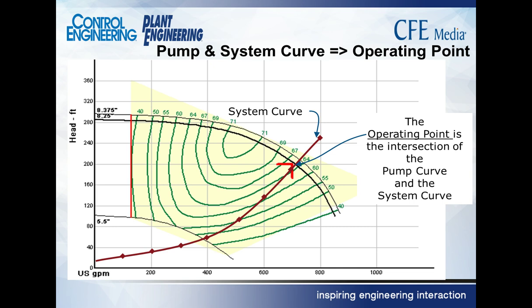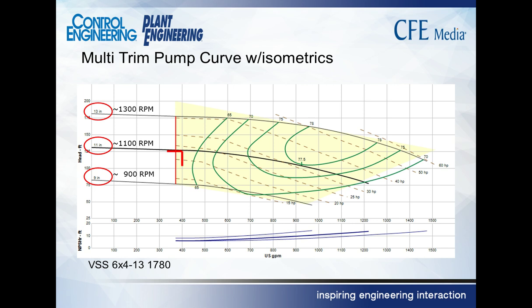Okay. The green lines are isometric efficiency. Think of it like a mountain. And the little semicircle right there at 71, that's 71% efficient. If you're anywhere on that green line, you're 71% efficient. As the efficiency falls off and you come down to 69, 67, 64, you're walking down the mountain, and the efficiency is dropping off. So at our operating point, we're just a little slightly above 64% efficient. Okay? The dashed line, and I'm not sure that this is the one that he was talking about. What if we got this one up here? Is this the one you may have been asking about?